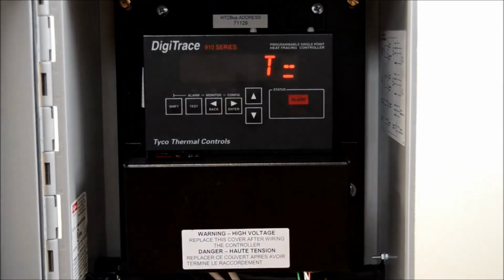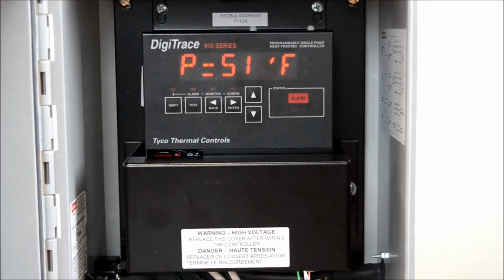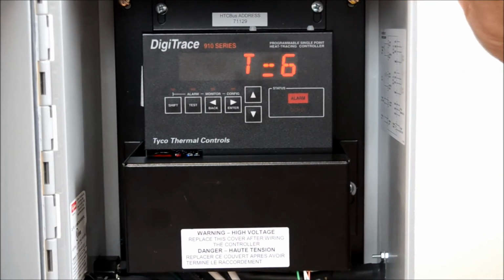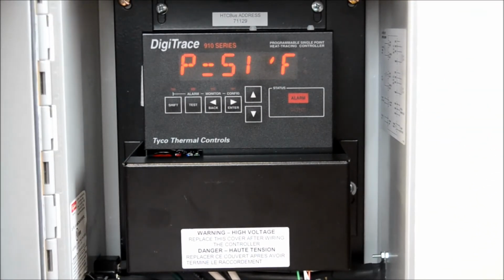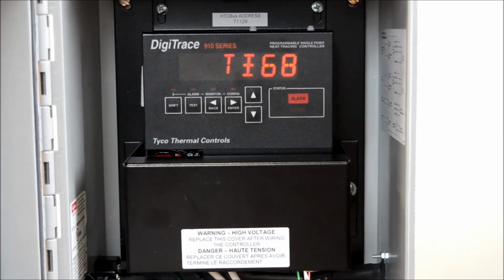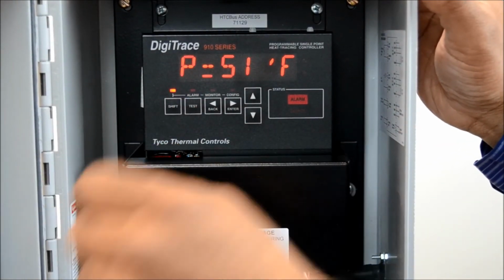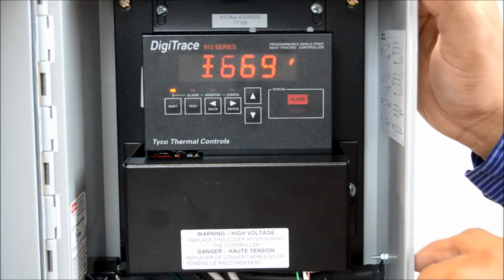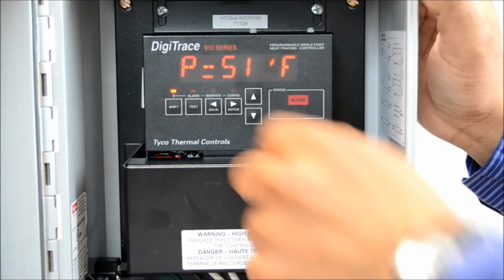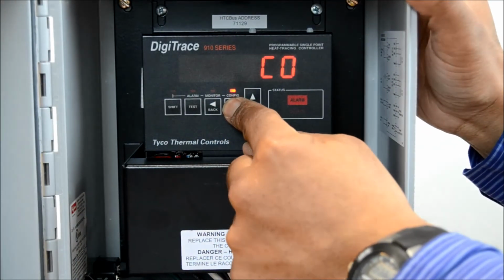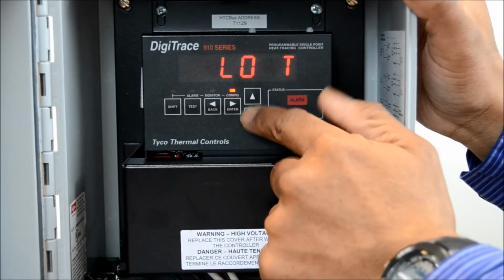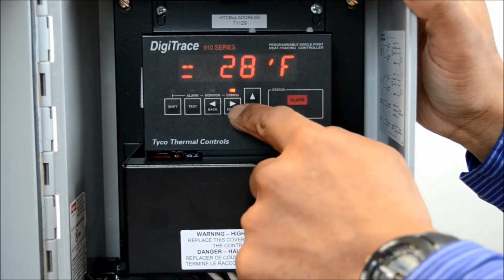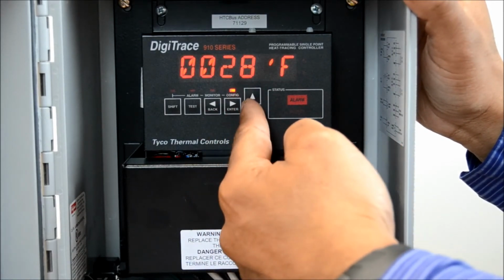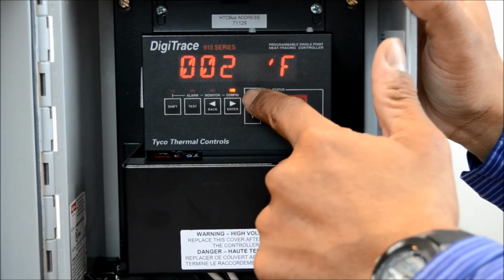Okay, so now we've learned about how to change the set points within this 910 controller. Now we're going to go over an alarm. I'm going to purposely set this into an alarm, and then I'm going to see if I can clear it. So I'm going to go to Shift, and this particular alarm setting that I'm going to set is the low temperature alarm. So I can go into the programming, and I'm going to go down to low temperature. Right now I have it at 28 degrees. I entered the function by hitting enter again, or hitting the mode.